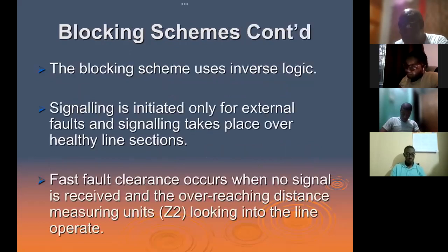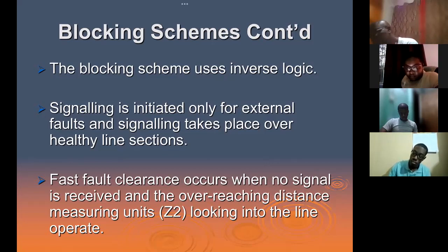So the blocking scheme uses what we refer to as inverse logic. We get signals if and only if the fault is external. So it's going to send a signal if the fault is external.